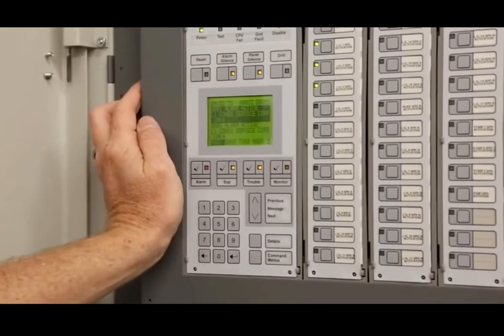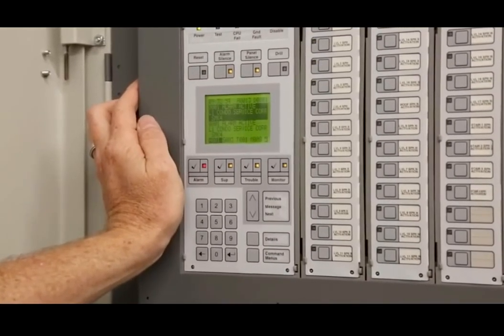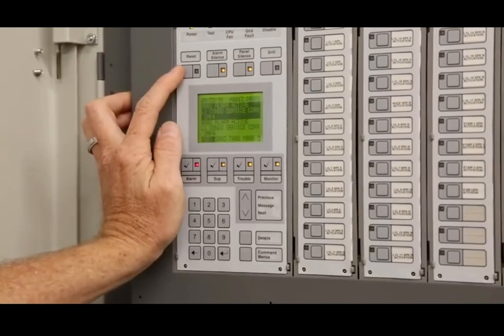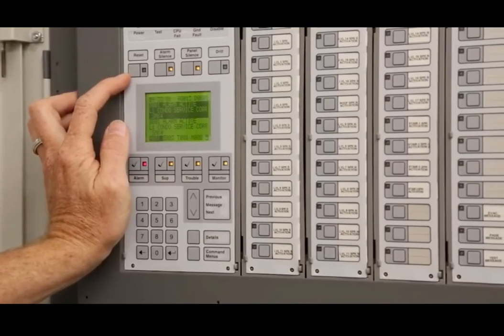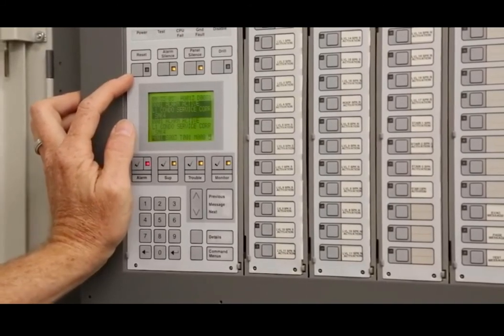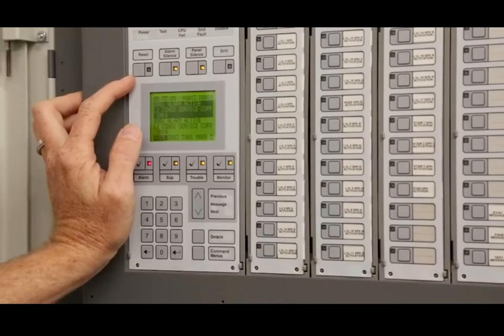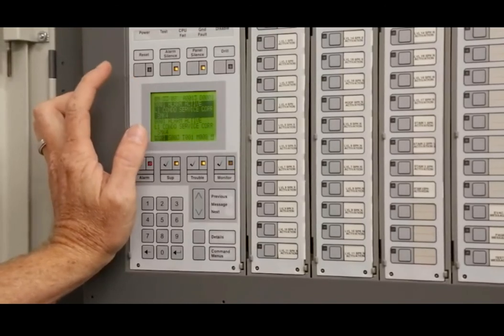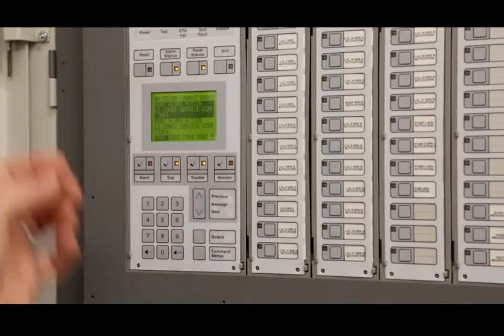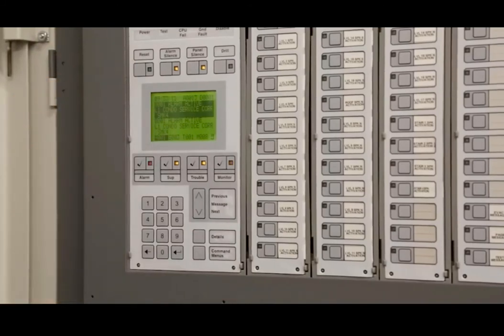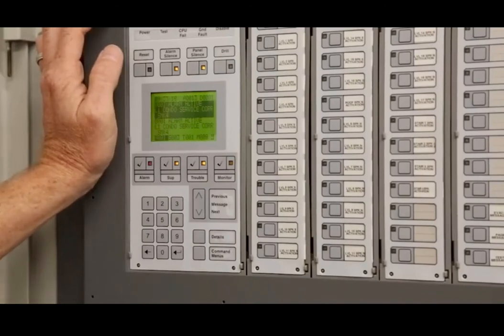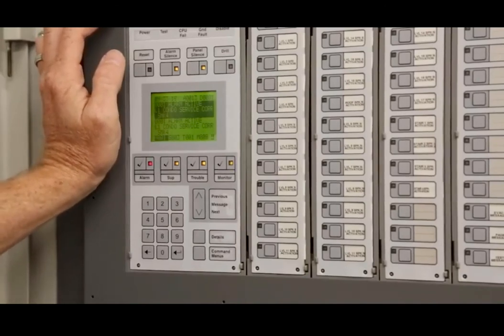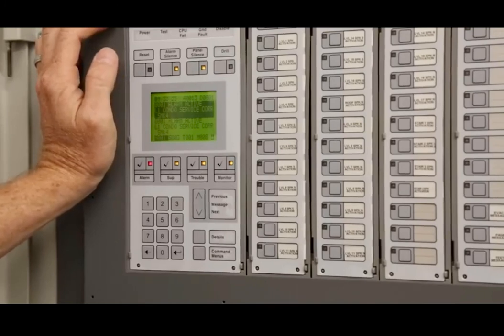You investigate it. There's no more smoke there. You can hit reset. Now, if the smoke detector still has smoke in it, it will not resound or refire if there's smoke in it, and it's still an alarm. Some systems, you hit reset and all of a sudden it'll re-trigger and everything will go back in alarm. If that detector still has smoke and you hit reset, it'll just stay the way it is, okay? We'd have to bypass it or something. But what I'm getting at, it won't re-fire.